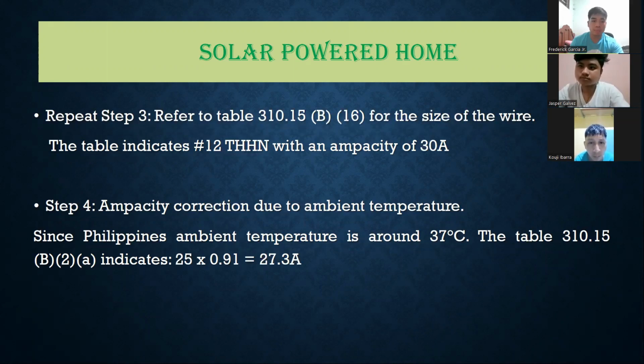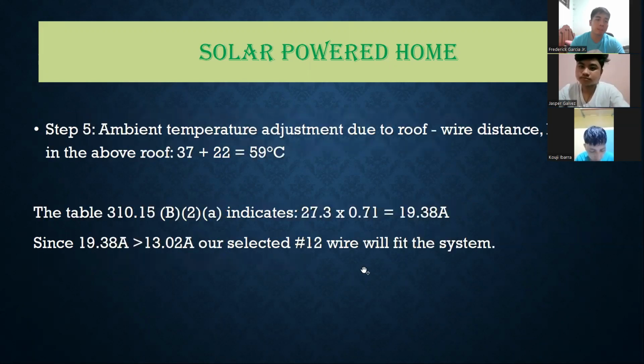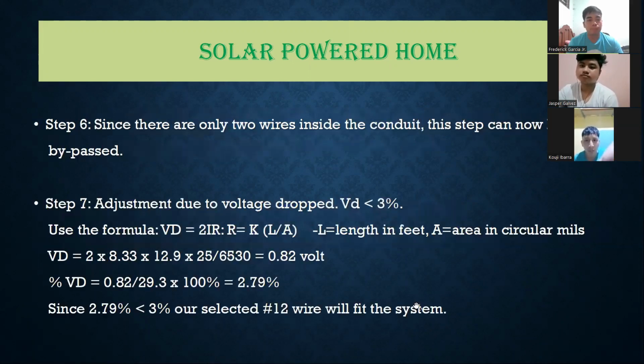So let's repeat the steps. This time, let's go for the number 12 with an ampacity of 30 amps. Now we repeat the previous steps. For step 4, for the ambient temperature ampacity correction, 30 times 0.91 is 27.3. Step 5, 59 degrees again, 27.3 times 0.71, we have 19.38 amps. Now we can see here that 19.38 is greater than 13.02. So the number 12 will fit the system.